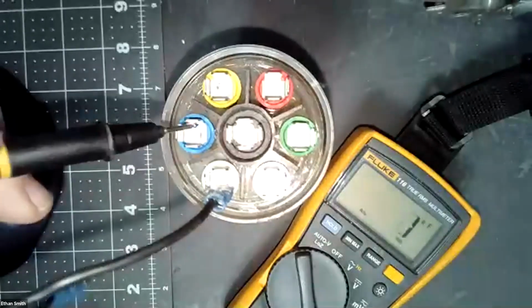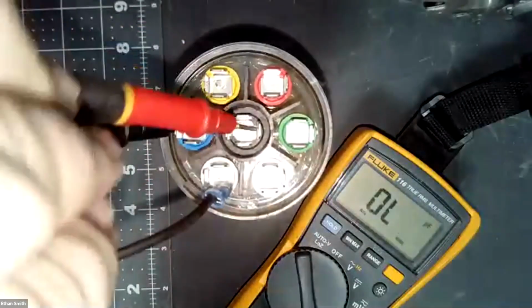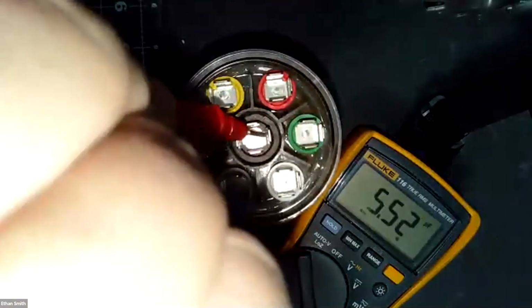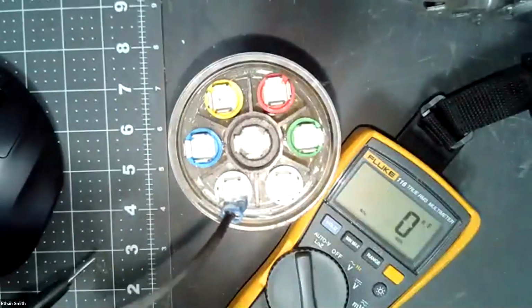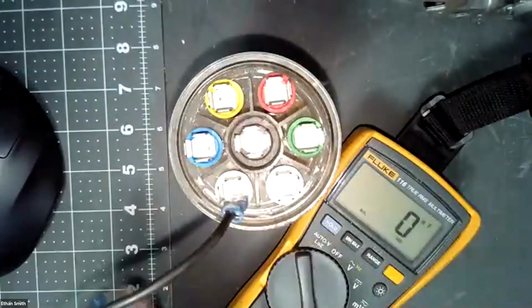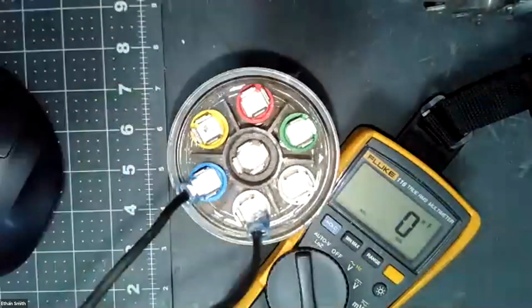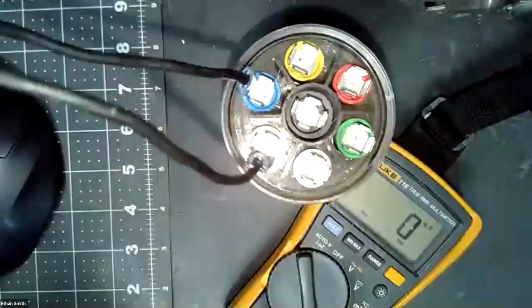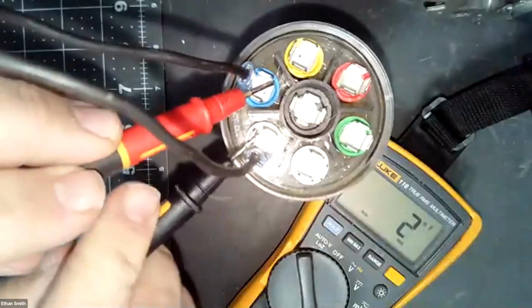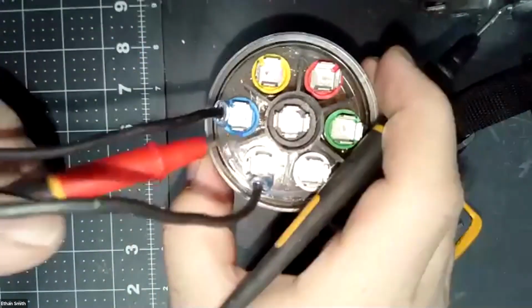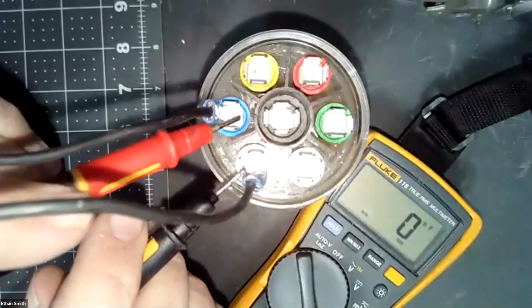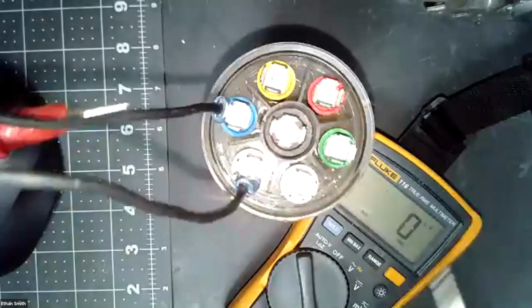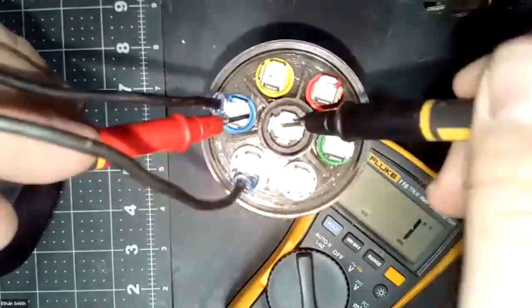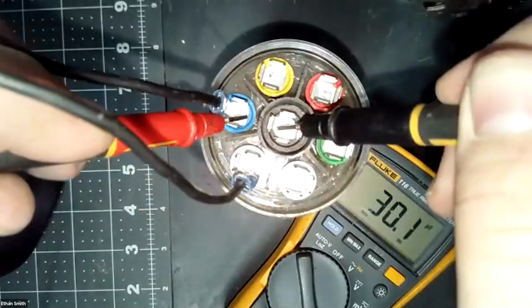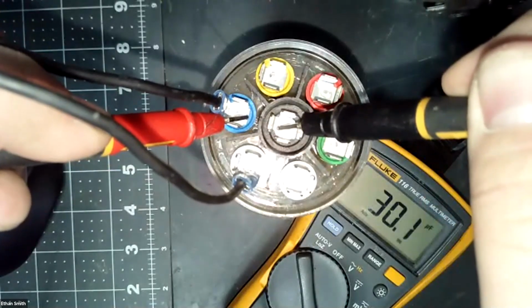So let's say we need a 30. There's definitely not a 30 capacitor in here. So I've got 25 there and I've got 5 here. What I can do is, because this port is tied to both of these, I can make it a parallel circuit just by putting this jumper wire between the 2 sides. And so now if I test between these 2 and actually get my probes on, come on. It's not happy with me. Oh, I can't test that way. I've got to test this way. I should get a 30 microfarad reading, which I do.